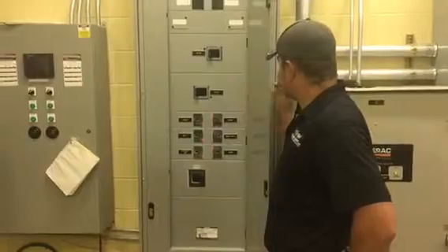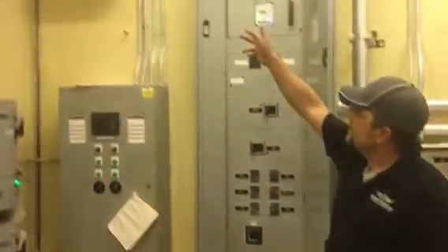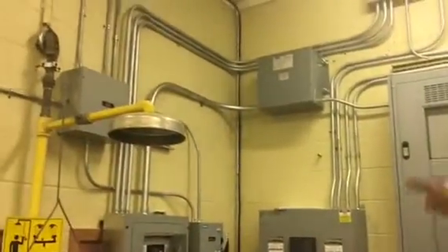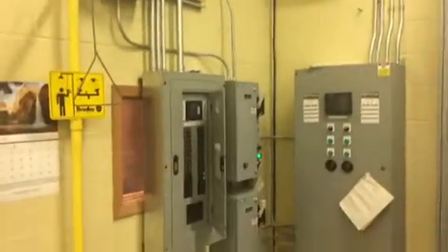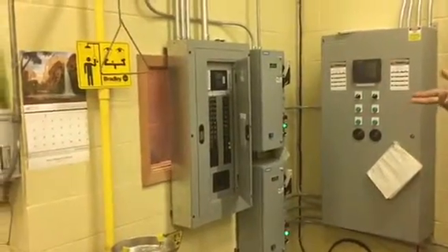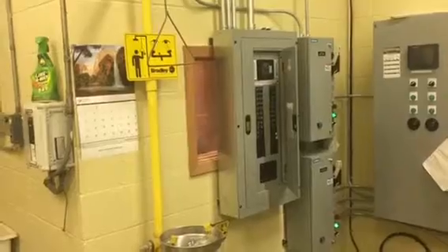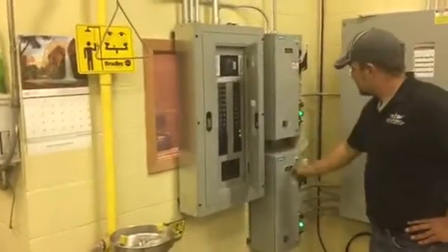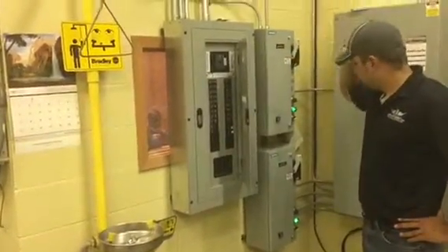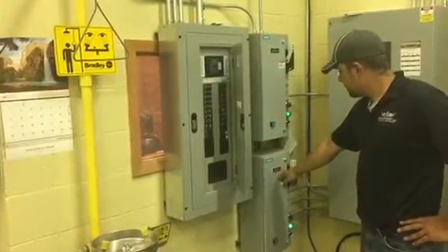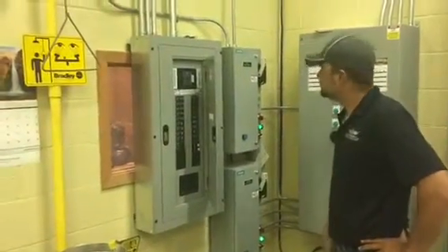In addition to the soft start upgrades, we also added a 15 kVA transformer, which basically feeds the house panel for all the branch circuitry inside the well house, inside the chlorine room. As you can see here, we also have motor starters that we installed, one for the exhaust fan for the main well room, and then the chlorine booster pump, which is to be controlled via SCADA.